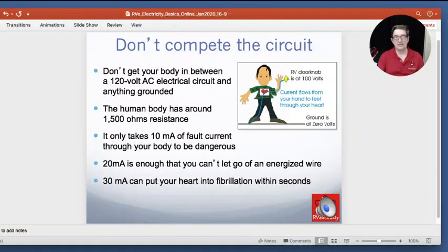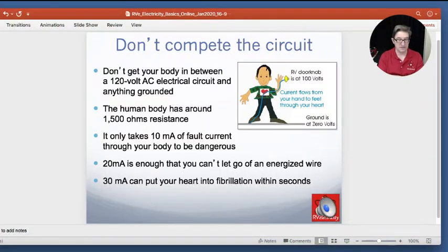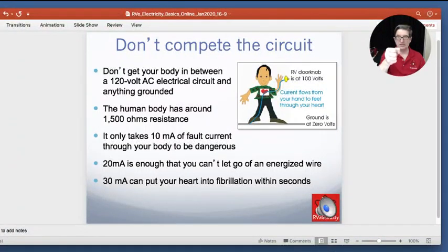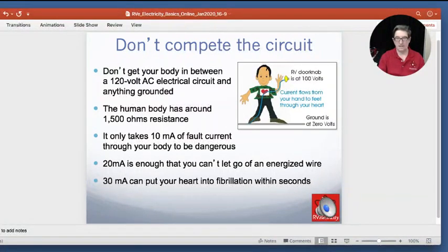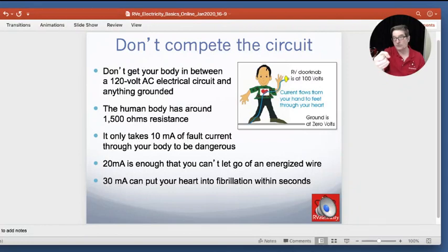Only 10 milliamps of fault current through your body can be dangerous to your heart. 20 milliamps is enough that you can't let go of an energized wire — I've actually experienced that, where you grab onto something and your hand just clamps and you cannot let go. It's the most terrifying thing. That's because you have more muscles in your hand to clamp together than to open up, so once you get about 20 milliamps going through you, all of your muscles clench up and you can't let go no matter how strong you are.